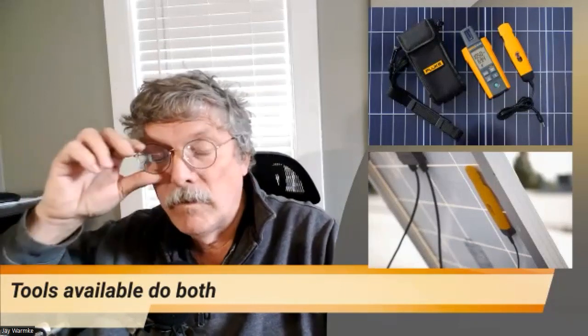All right, so armed with this information, before I get into this, they do have these kits. This is a Fluke kit where you can use that irradiance meter, but it also has a connected thermometer that you can just attach to the back of the solar panel, and you can get all of your readings at once. In fact, I think this thing even has a data logger, so you could record that. So when you're commissioning your system, and you need to give a report to somebody, you'll have that you can print out. It will also track the angle and the azimuth of your array. It'll put all of that information in there as well. So a handy little tool, but those of you who have bought Fluke tools know it's going to be a wee bit pricey. So there are other alternatives. You can get some cheaper meters. You can get one of those handheld infrared thermometers, and that's sort of the poor man's way of doing it.